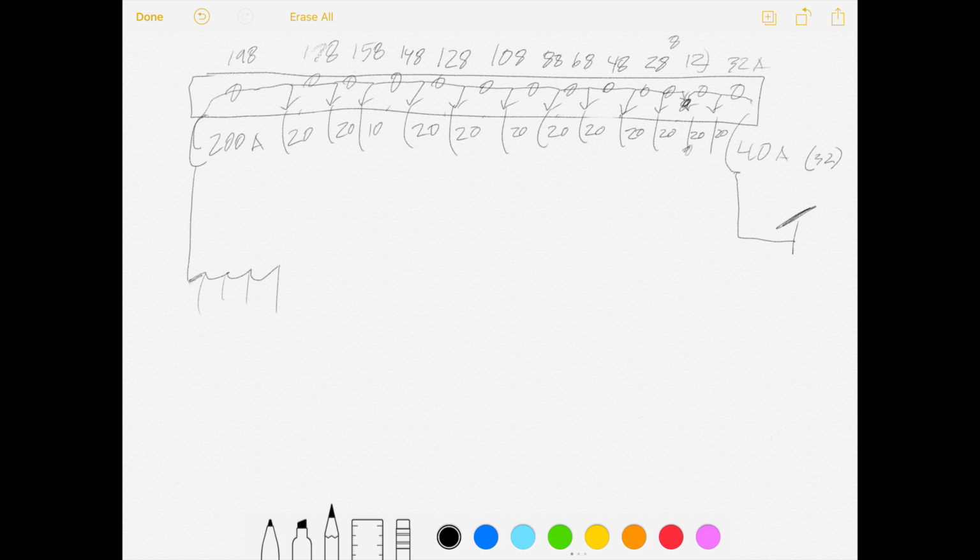So as you can see, at no single place on this bus bar is the rating being exceeded at all. That is the logic for why we can exceed the total capacity of our bus bar as long as our sources are coming from opposite ends. I hope that makes sense.